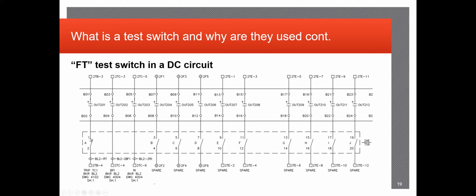So if this knife switch was to be closed, this relay was put in service and it detected a fault, this output would close, cause the circuit to make up and go all the way out to the breaker and open the breaker. If that relay is placed in service and this switch was open and it identified a fault, that output would be made up, but the break in the circuit would not allow the breaker to trip and could cause some pretty substantial damage to the breaker, depending on how aggressive the fault is.